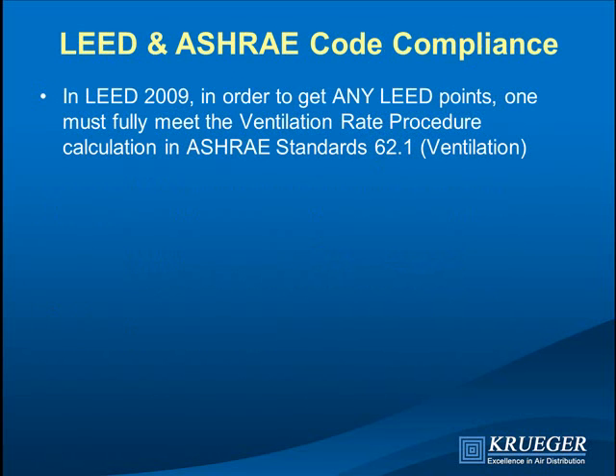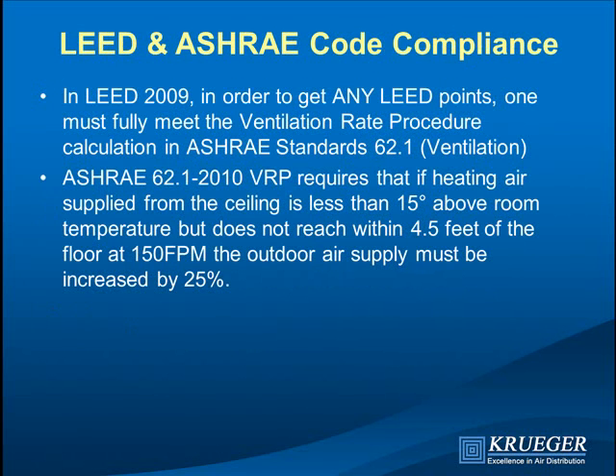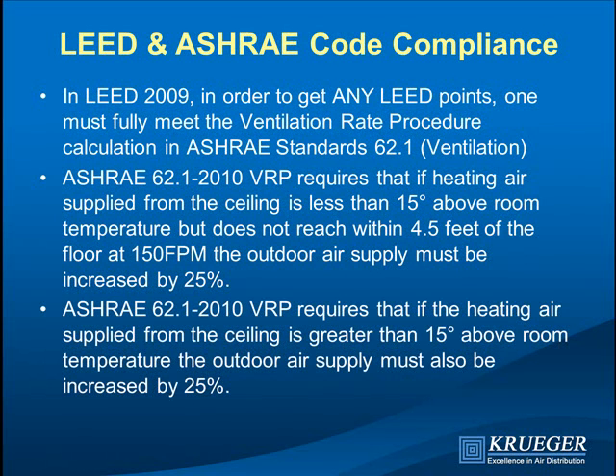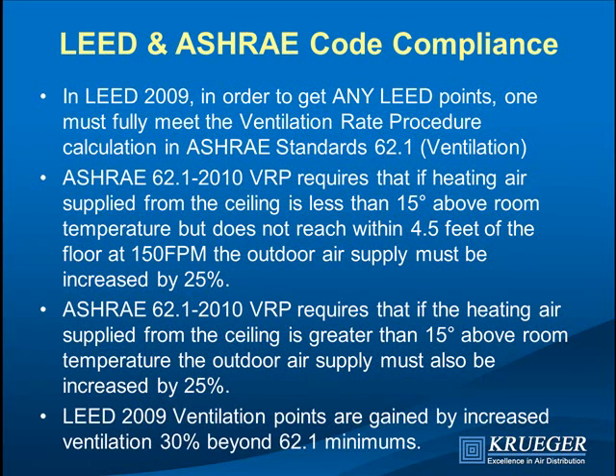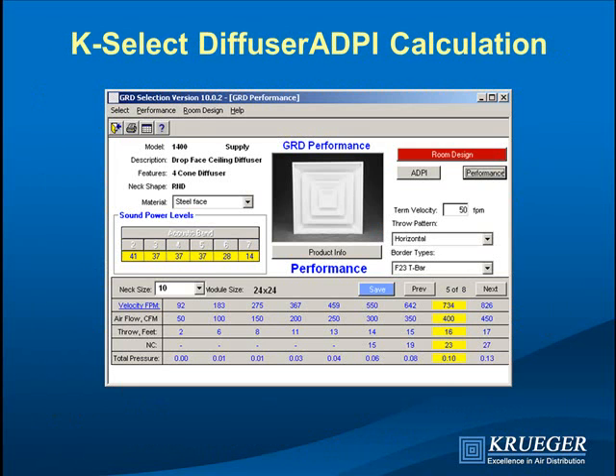LEED will give you a point for complying with relevant standards. Complying with 62.1 is a prerequisite and is in code. The ventilation rate procedure states that if the heating air is less than 15°F above room temperature and doesn't make it to the window, you must increase airflow by 25%; and if it is 15°F above room temperature regardless of where it goes, you must increase the air supply by 25% to address short-circuiting. This is code, not a suggestion. LEED 2009 also gives a point for increasing ventilation 30% beyond minimum.